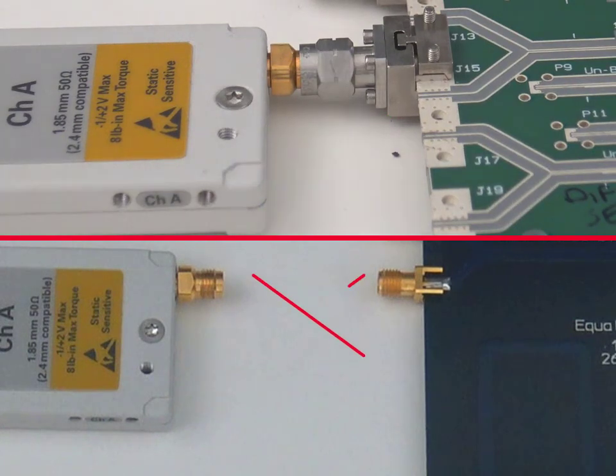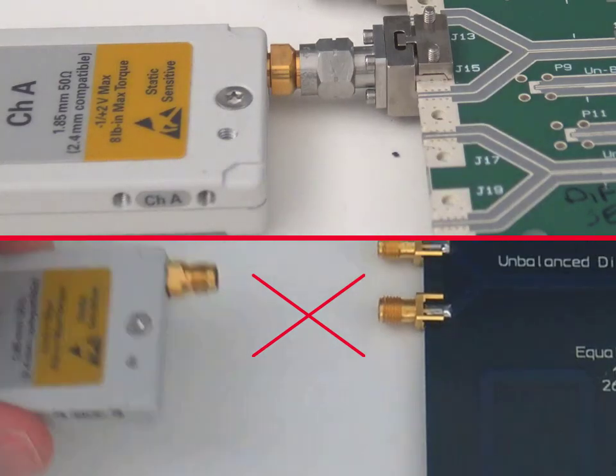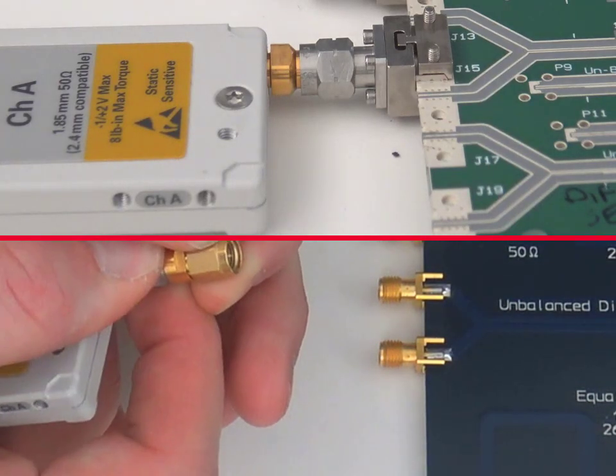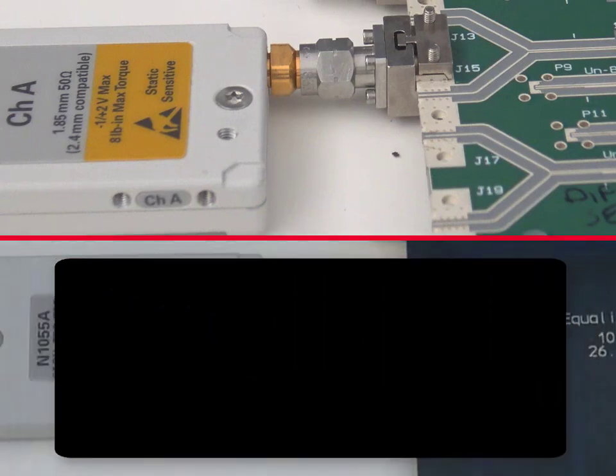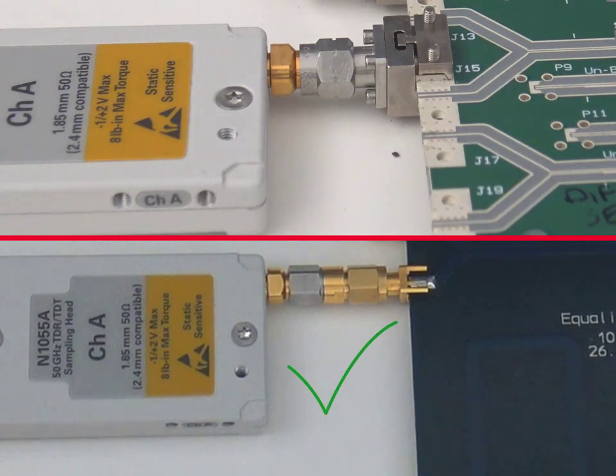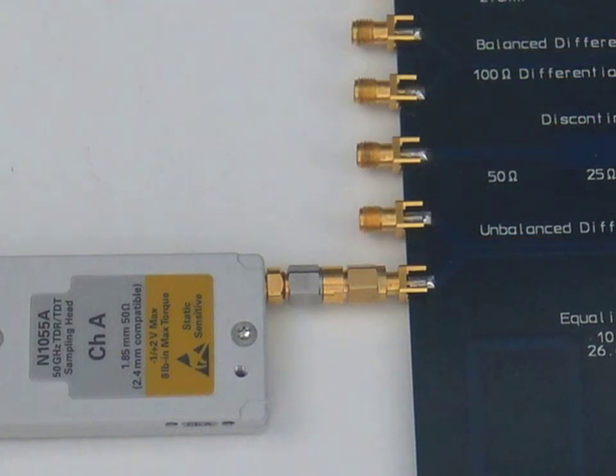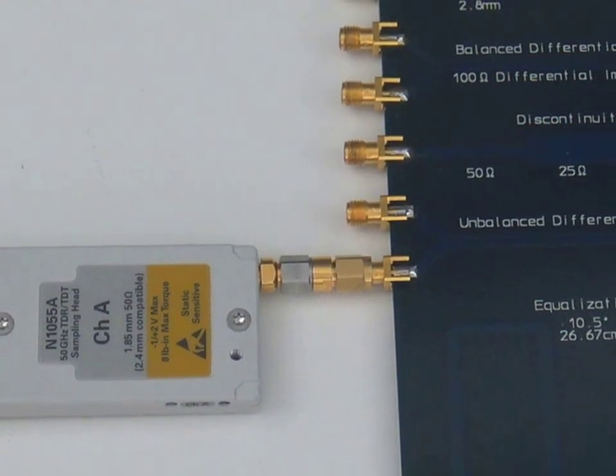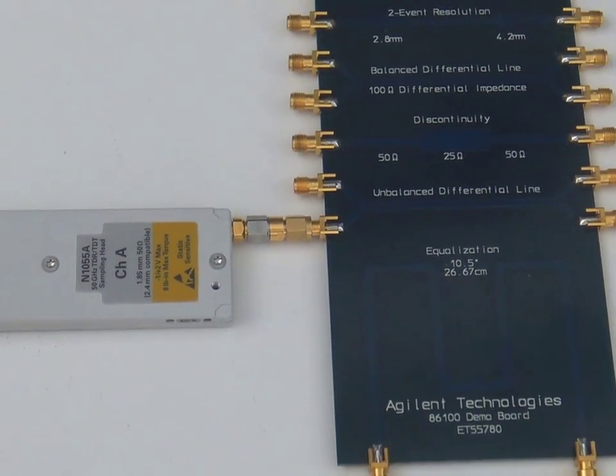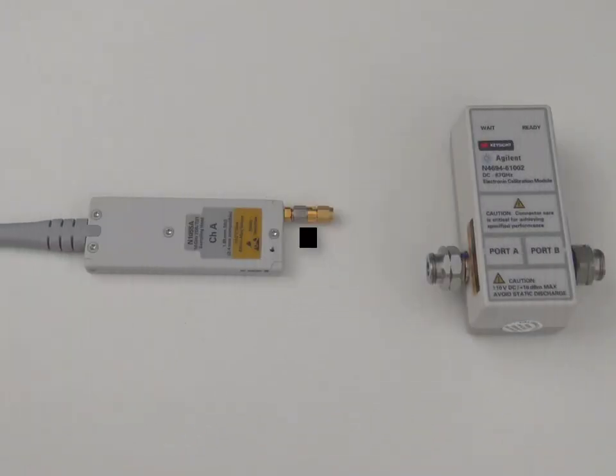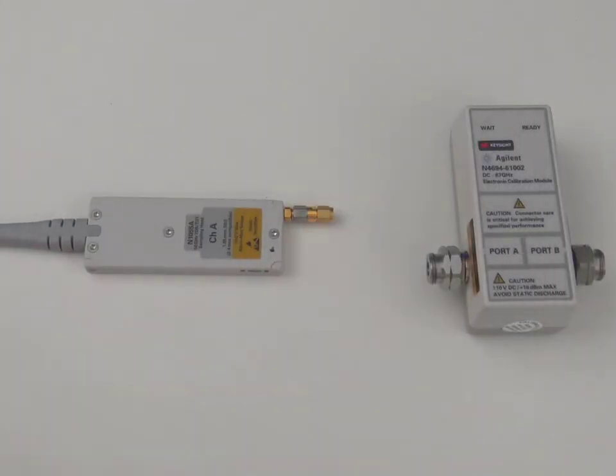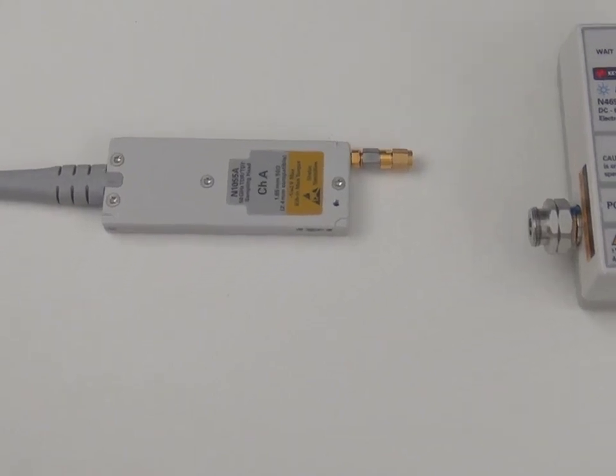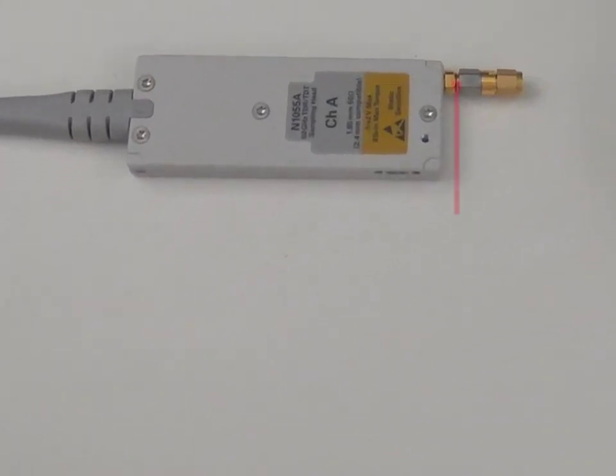If your measurement head does not connect to your device under test, then you must add an adapter to connect your measurement head to the DUT. In order to make sure you are measuring only the DUT and not the adapter, you must use the eCal to shift the measurement plane up to the mate point of the adapter. This means that your measurement head will be calibrated to use the adapter to make TDR measurements.